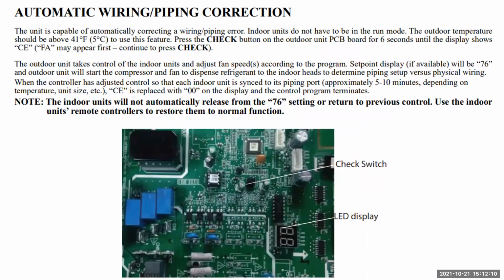Now on the multi-zone systems, usually the MGRs, there is an automatic wiring and piping correction. It is not recommended that you do this. Go ahead and unhook the wires or the piping and put them in the correct spot. This will avoid any future problems you could have if you had to change out a board, a head unit, the outdoor unit, or anything like that.